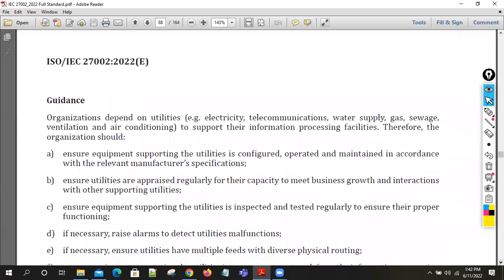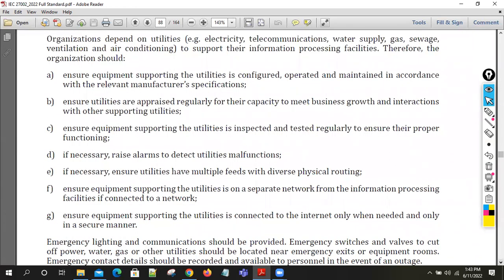Sometimes electricity doesn't go for months, 2 months, 3 months, there is no power cut. In that case, people tend to say they don't have any power cut in their area, so why should they have these kinds of backup? But that doesn't mean the power cut would not be there. It could happen. So for that purpose we should have these facilities, and they should also be tested. If electricity hasn't gone off in your area for a year, that doesn't mean you should rely on your UPS and diesel generators without testing, since they haven't been used even once in that time.